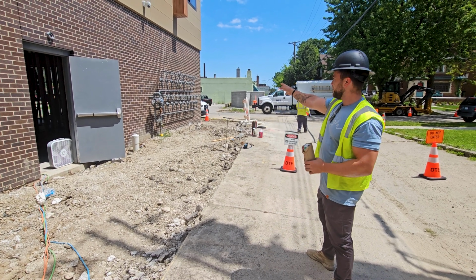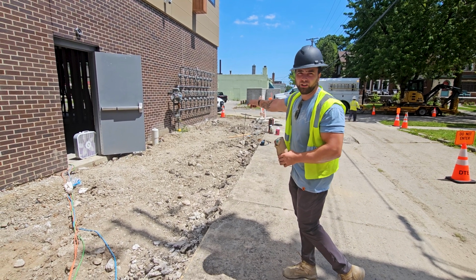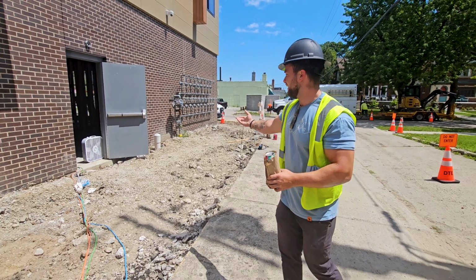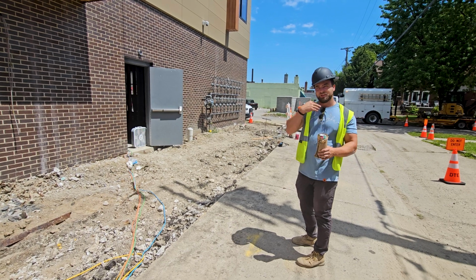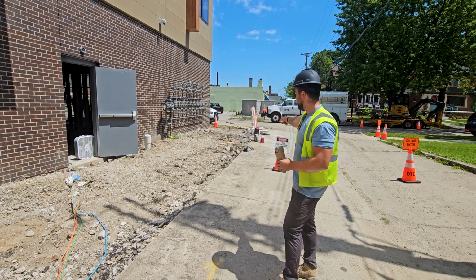We've got all of our gas manifolds and meters installed right now. And then you'll notice that the main gas line, right where that yellow collar is at, that's where the main gas line connects and goes underground. Right now, the gas line is shut off to all the meters, but we're still smelling some gas. So we know now that there's a leak in the installation underground somewhere.